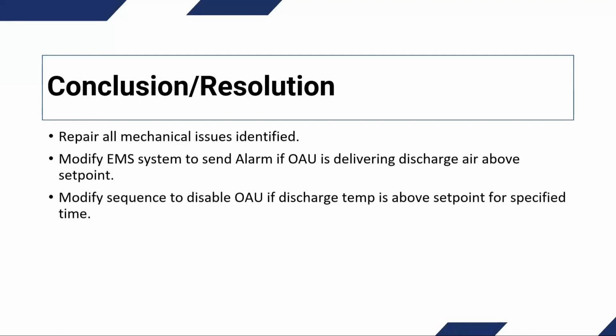We also modified it to where if it couldn't meet discharge air for an extended period of time, it would just shut down the unit, because with that unit delivering so much outside air that was unconditioned, that was really humid, it would really raise the humidity levels quickly in that building, to the point to where you'd have books curling and potential growth inside the building, which of course we don't want. So we had it modified to shut the units down if the units couldn't deliver the right amount of outside air or temperature of outside air.